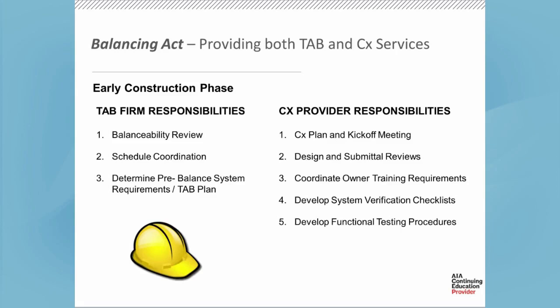The other thing here, on the TAB firm side, at this stage of the project, they really should be working on schedule coordination, both with their commissioning counterparts and, most importantly, with the project team. We see more issues arise on projects from a lack of knowledge of what is needed for the TAB activities to take place, and the commissioning activities for that matter. Even more so, we see a lack of understanding on the construction team, and it's not their fault - they just may not know what is required for testing and balancing activities to begin, and what kind of support is going to be required thereafter so they can complete their activities. That's really what we're talking about with schedule coordination.